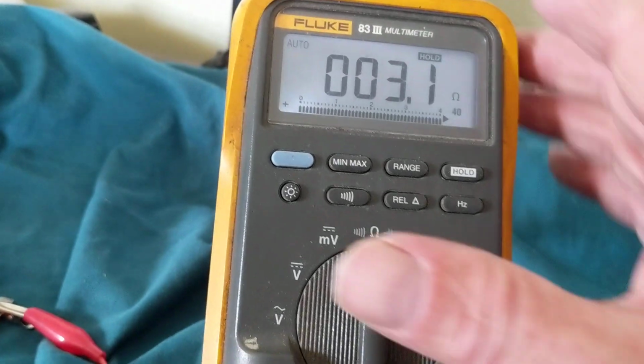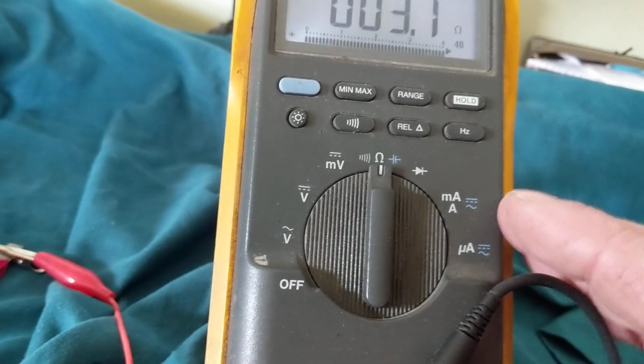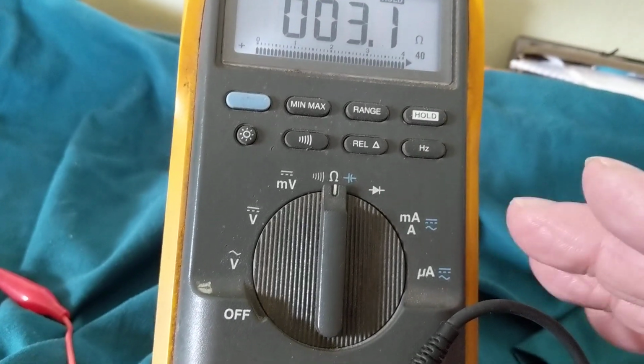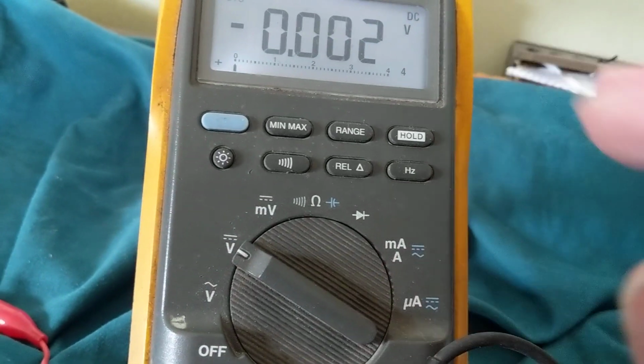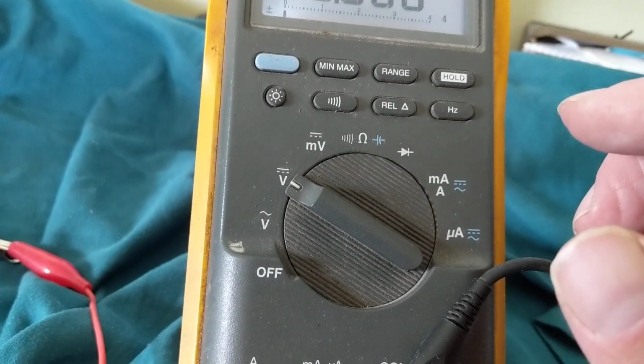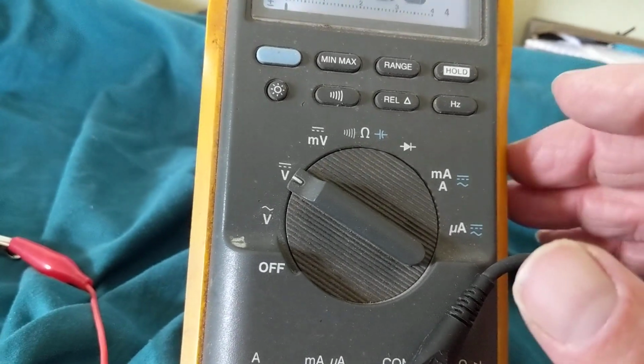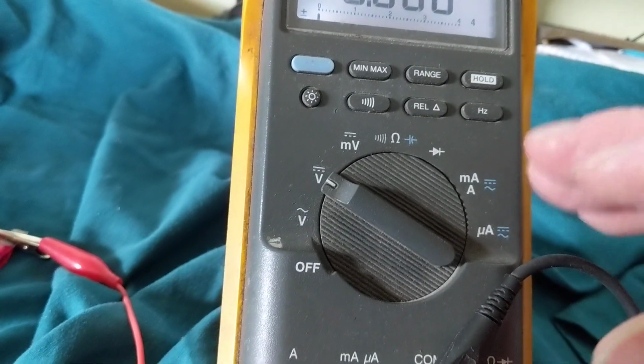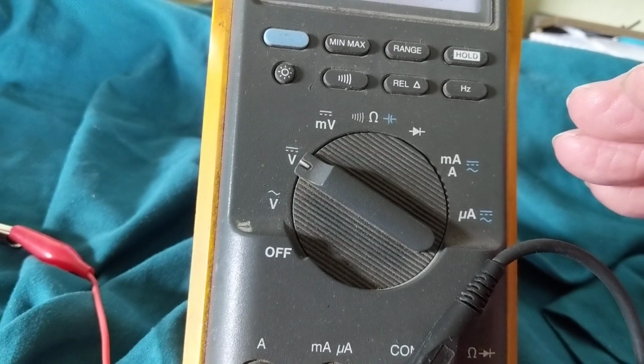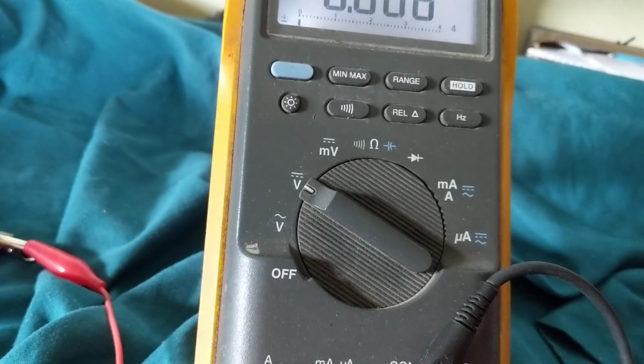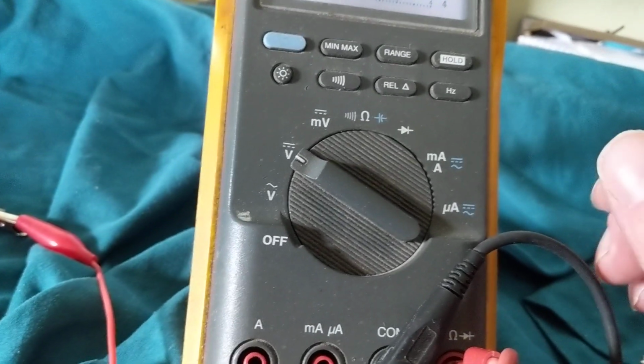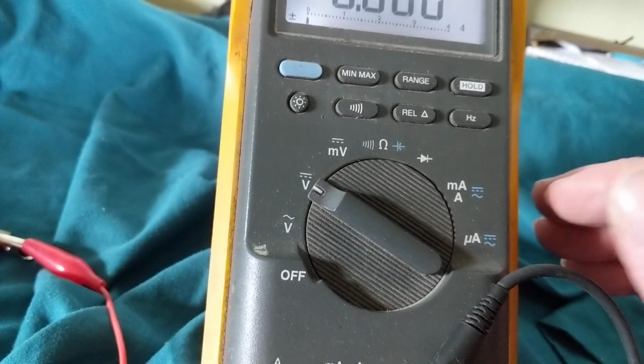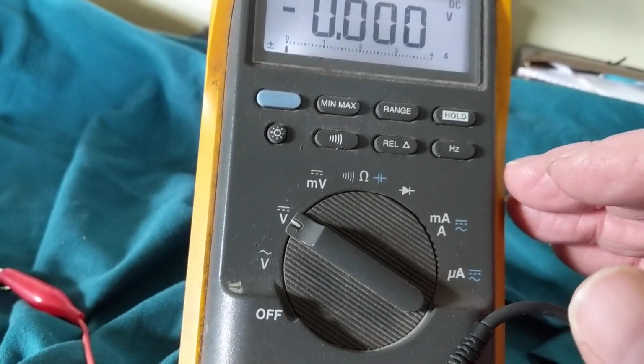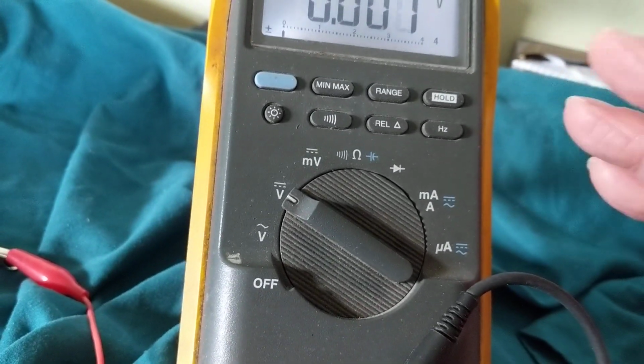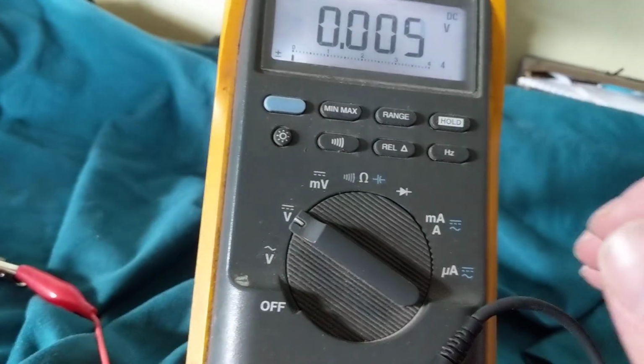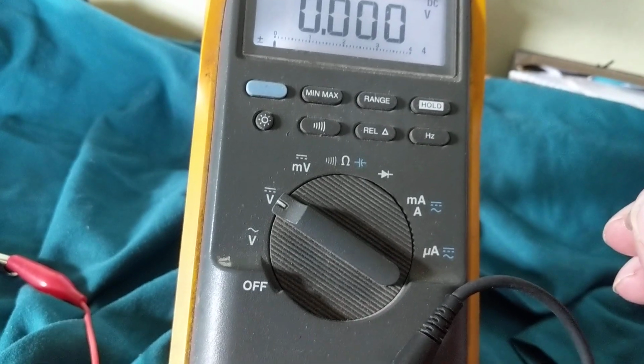But the point is, multimeters have to be calibrated. You have to make sure that when you measure DC volts and it measures 12 volts from the battery, it's giving you an accurate measurement. So in industries and other places, you send it out for calibration. A company does calibration on all equipment: oscilloscopes, analyzers, generators, or even soldering stations. If the soldering station says 700 degrees, I want to make sure it's 700 degrees and not 800 degrees. Otherwise, you burn components. So calibration is needed, and to show it is accurate, they put a sticker on it. They do an inspection, just like they do an inspection on your car. That way you know that if I'm measuring 12 volts, the component is 12 volts. Otherwise, you'll get inaccurate measurements.